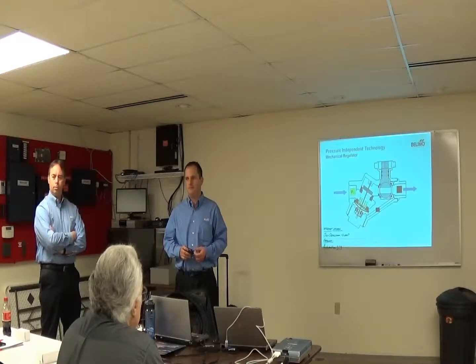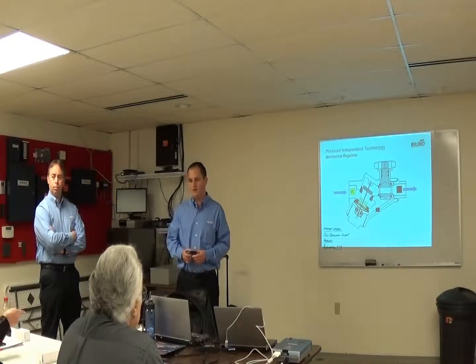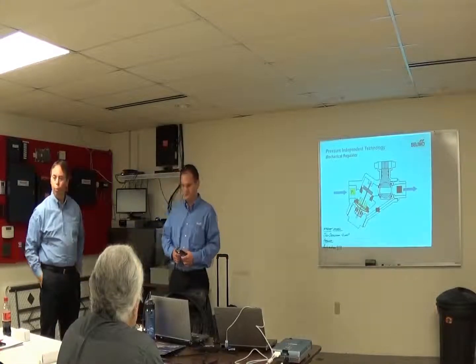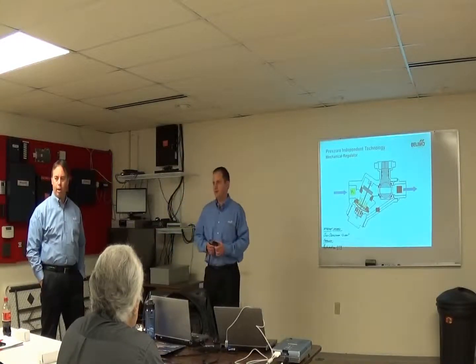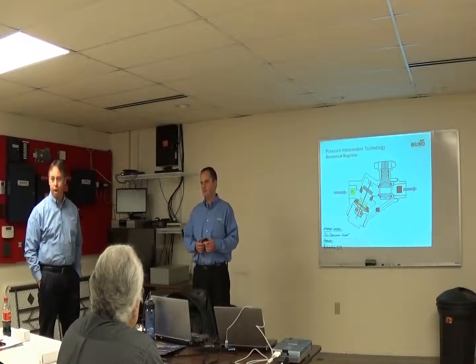That's after they've reduced. So if you put a 1/2-inch valve on a 1-inch line, then you have to have 5 pipe diameters of a half inch, so it's 2.5 inches. Right, 2.5 inches. Right.